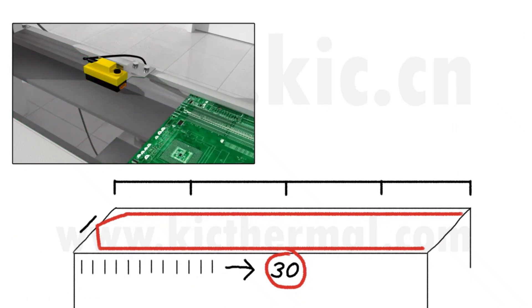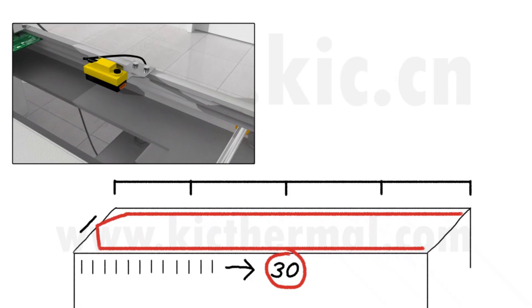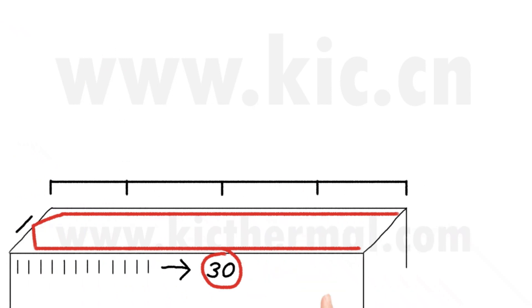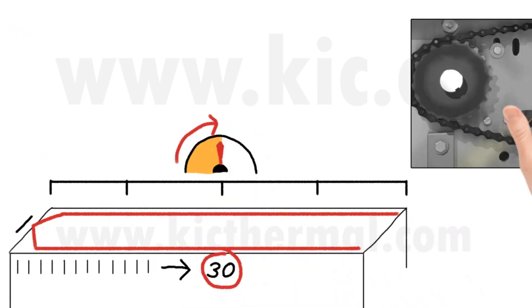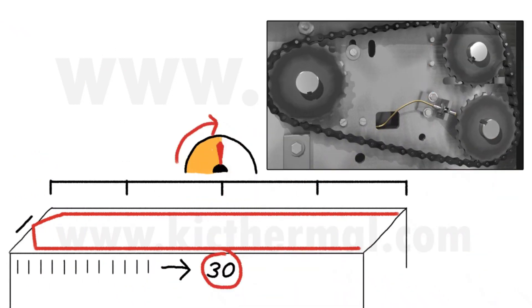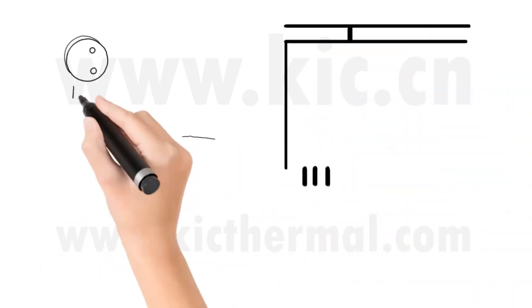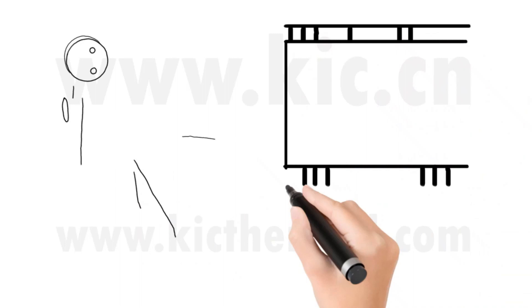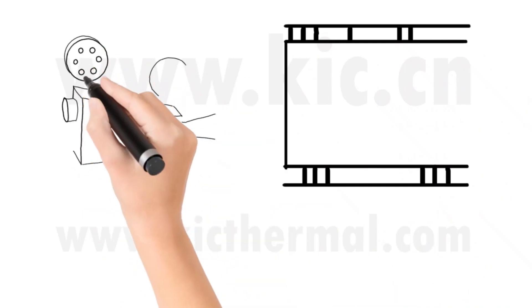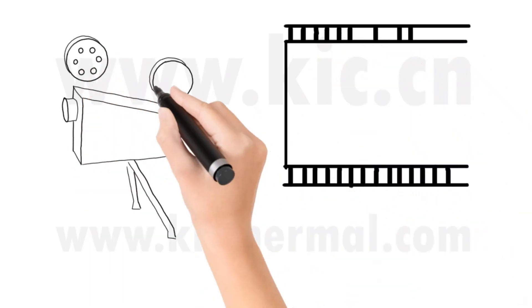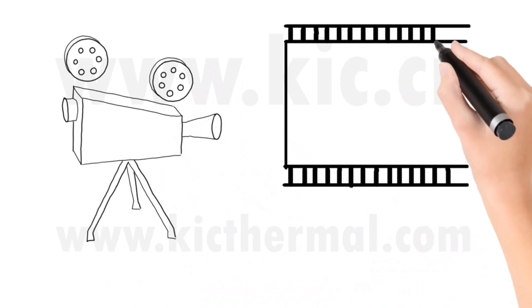The KIC Automatic System also uses a board sensor at the entrance of the oven to determine when the board entered the oven and to calculate the real-time process data. The KIC Automatic System uses a speed encoder sensor installed directly to the oven conveyor drive to continuously monitor the oven conveyor speed. The combination of these sensor inputs allows the KIC System to know precisely where the board is at all times and accurately measures and calculates real-time changes in the thermal process.